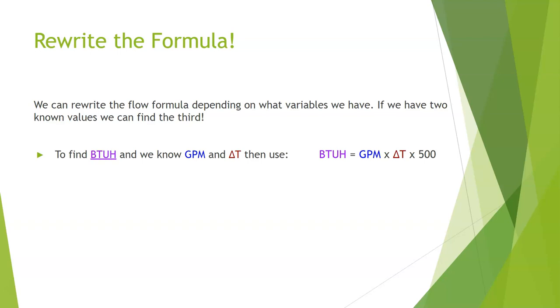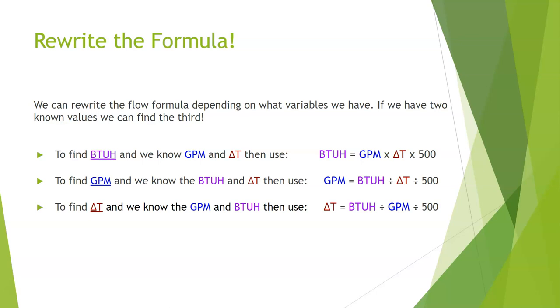The formula we've been using so far is to find BTU when we know GPM and delta T: BTU equals GPM times delta T times 500. But if we want to find GPM and we know BTU and delta T, then we use GPM equals BTU divided by delta T divided by 500. If we need to find delta T and we know GPM and BTU, then we use delta T equals BTU divided by GPM divided by 500.